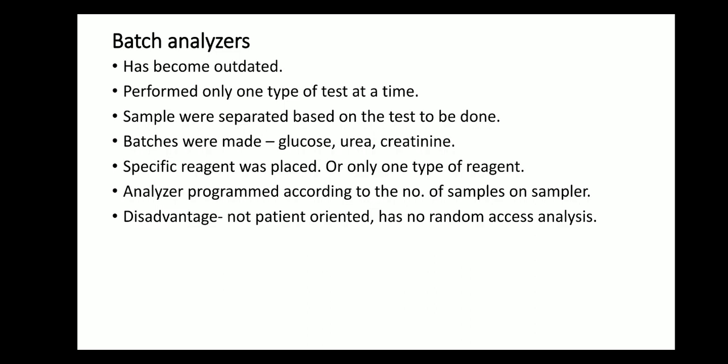So in the batch analyzer, one type of test is done at a time. Okay, and you have to separate the samples. All the samples that require glucose analysis, you have to separate and keep. All the samples that require urea, you have to separate. So at a time only one type of test can be done, and only specific reagent can be placed. So this has many disadvantages, so this is not being used. This has no random access analysis and this is not patient oriented also.